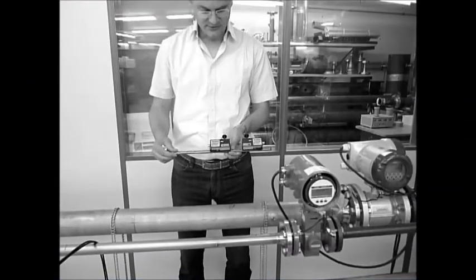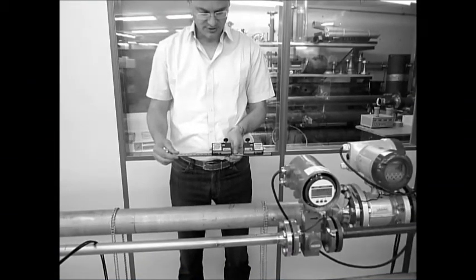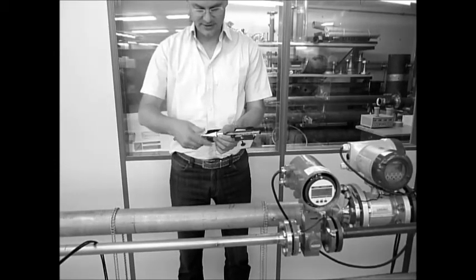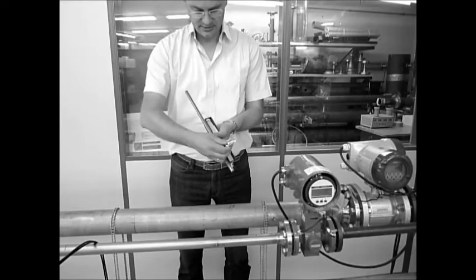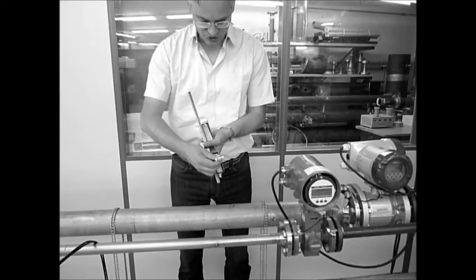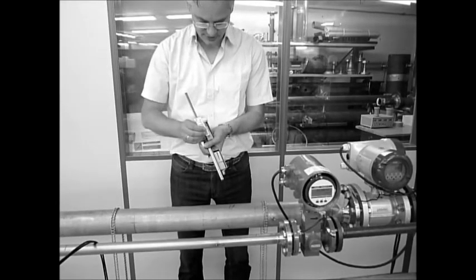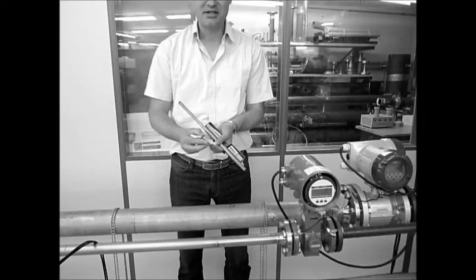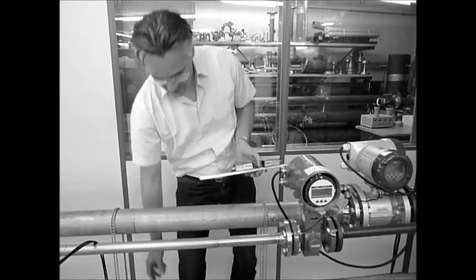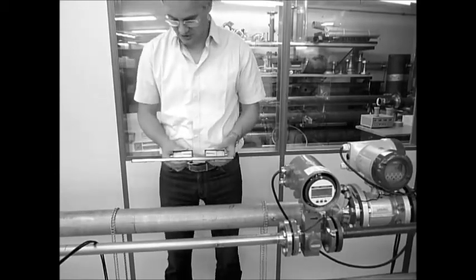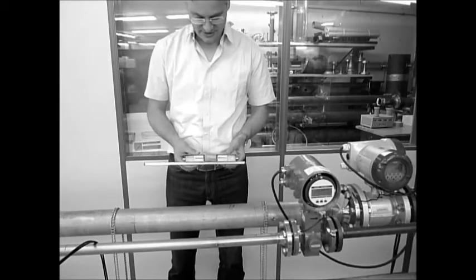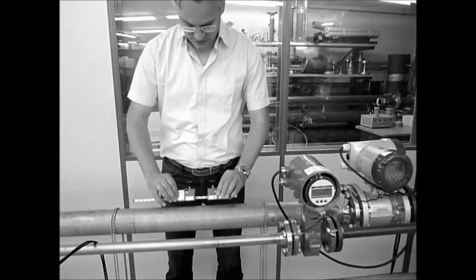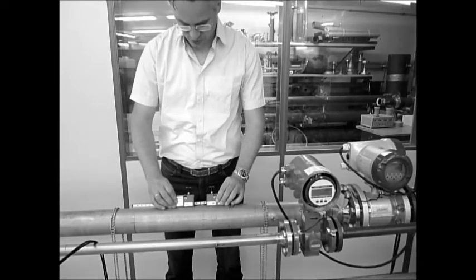Now we have to mount the transducers on the pipe. I'm using a little bit of the coupling compound - just use very little in the middle of the transducer, a line of two or three centimeters. Very little compound is good enough to give the acoustic coupling to the pipe. The transducers with the two screws can be very easily placed on the pipe.